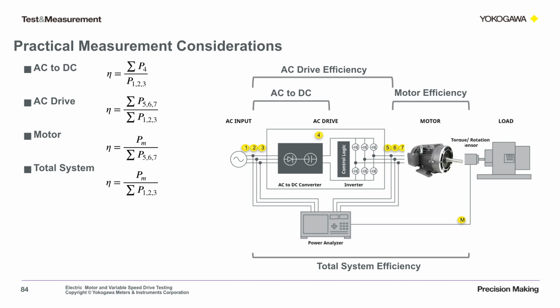In this 3-phase motor example, we have 4 different efficiency measurements we can make. For AC to DC efficiency, we want to see how well our circuit converts to DC using our rectifier circuit. For AC drive efficiency, we want to see how well we can measure the losses to the rectifier stage, DC stage, and IGBT stage. Motor efficiency will measure those losses attributed only to the motor, and last, we can measure the losses through the entire system.